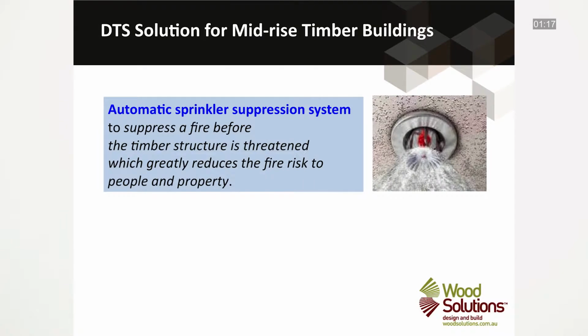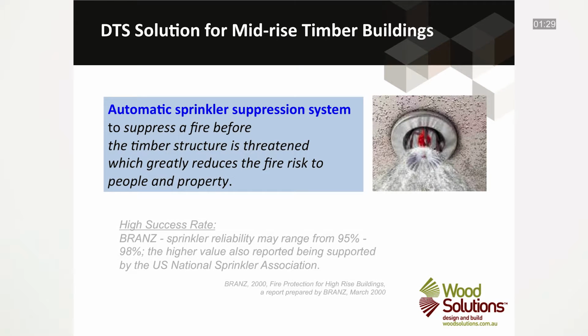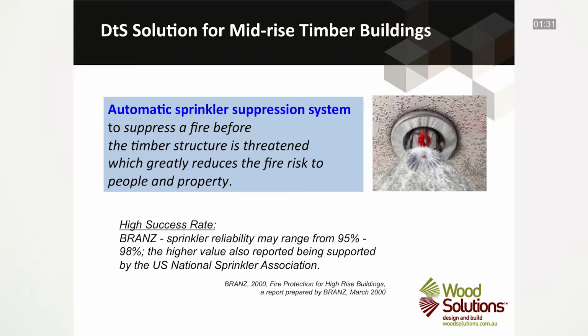The first level of fire protection comes through the use of automatic sprinkler suppression systems, whose function is to suppress a fire before the timber structure is threatened. It is widely known and accepted that sprinkler systems greatly reduce the fire risk to building occupants, their property, and to firefighters if they need to attend a fire event. Automatic sprinkler suppression systems have a very high success rate.